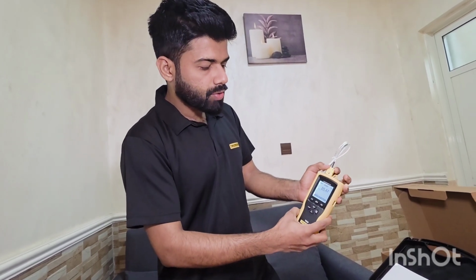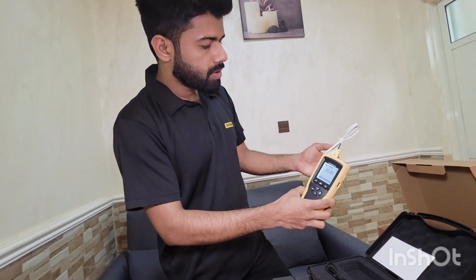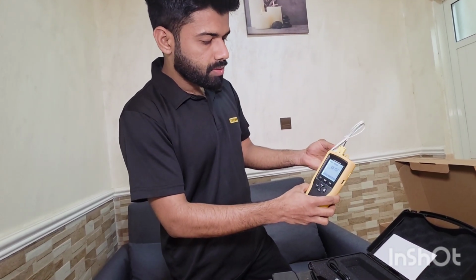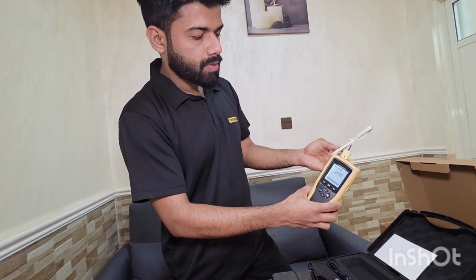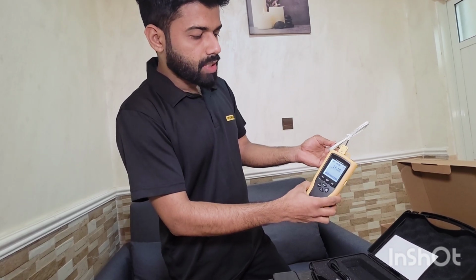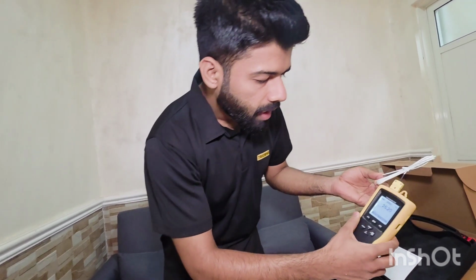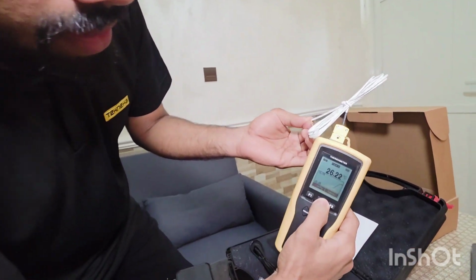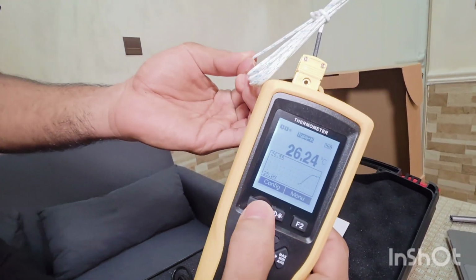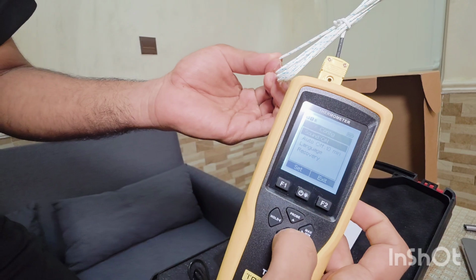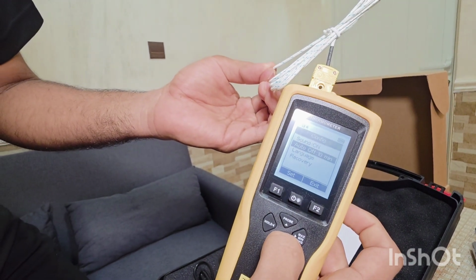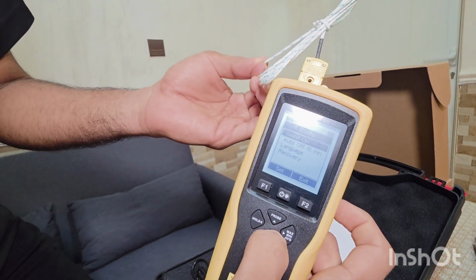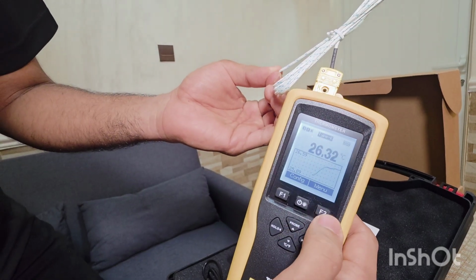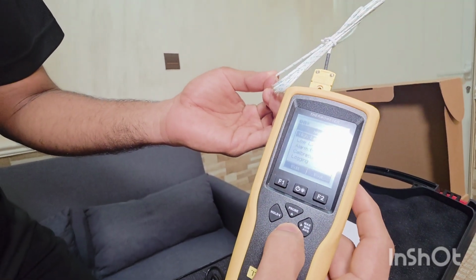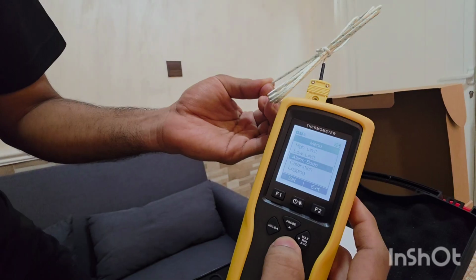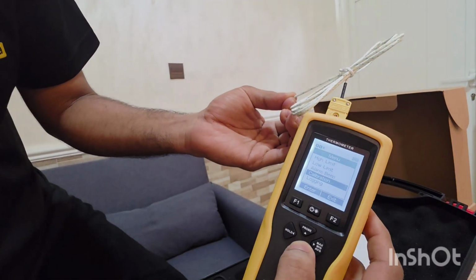Here it is now showing 25 degrees Celsius. If I touch here, it will go high. This is a single channel thermometer data logger, and there are options. This is an LED backlight, and you can see the configuration: sound on and off, auto off after 10 minutes, language and so on. Exit, then go to menu. There you can set the high limit, low limit, alarm beep, and there is a calibration option, and logging.